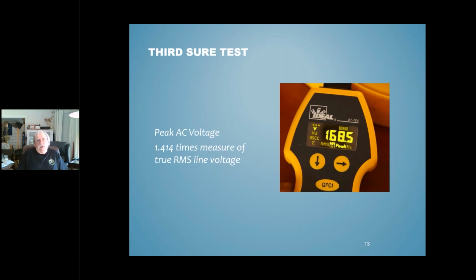And if you've got more than about a 2 to 4% variation, you're actually looking at what can simply be described as some distortion in the AC power feed, which again, unfortunately, is not that uncommon and can create some problems on board, particularly with things like audio amplifiers and stereo equipment and things of that nature. You get low-level hums in the background and symptoms like that. So it's a way of making a quick determination about possible line voltage distortion that you would normally need much more sophisticated equipment to even think about troubleshooting. But this will give you a clue.